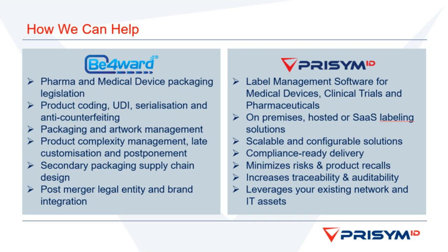Another area where there are significant new changes is in terms of electronic labelling, where there are a number of requirements. In the new regulations, there's a requirement that any information that's included on your labels will also have to be made available on your website for those products. As well as that, though, there's opportunities to improve your products and how your products are identified, and how users, whether it's end users or clinicians, can get information. And there's the new EIFU symbol that will be included as part of that.